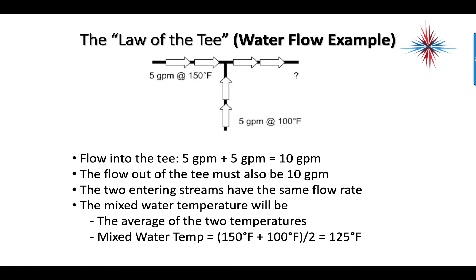Now we can add temperature. If we have five gallons per minute at 150 degrees Fahrenheit and five gallons per minute at 100 degrees Fahrenheit, we know our flow into the tee is five and five - that's 10 gpm. So the flow out of the tee must also be 10 gpm. Now we have a temperature to deal with. The mixed water temperature is the average of the other two temperatures because the flow rates are equal. So I have 150 plus 100, that equals 250, and I divide it by two because these flow rates are equal.